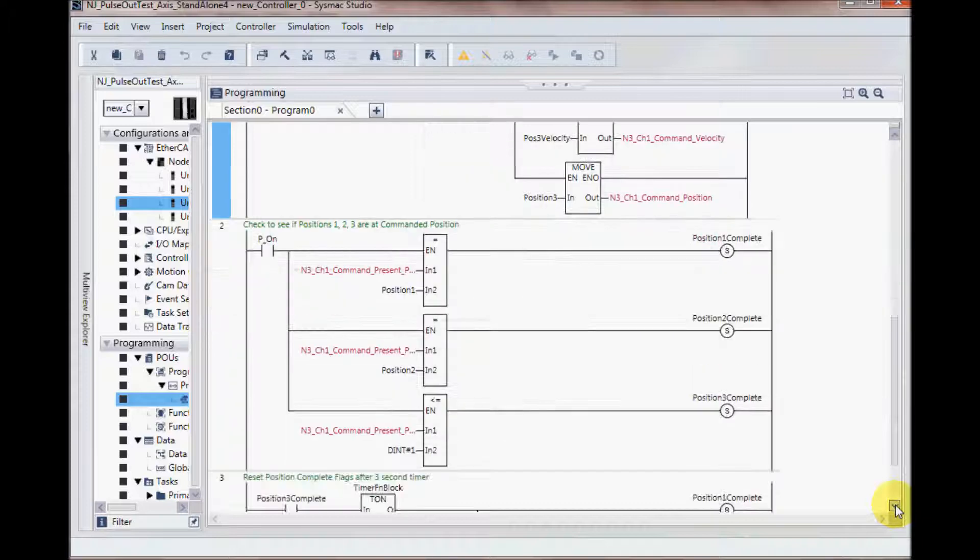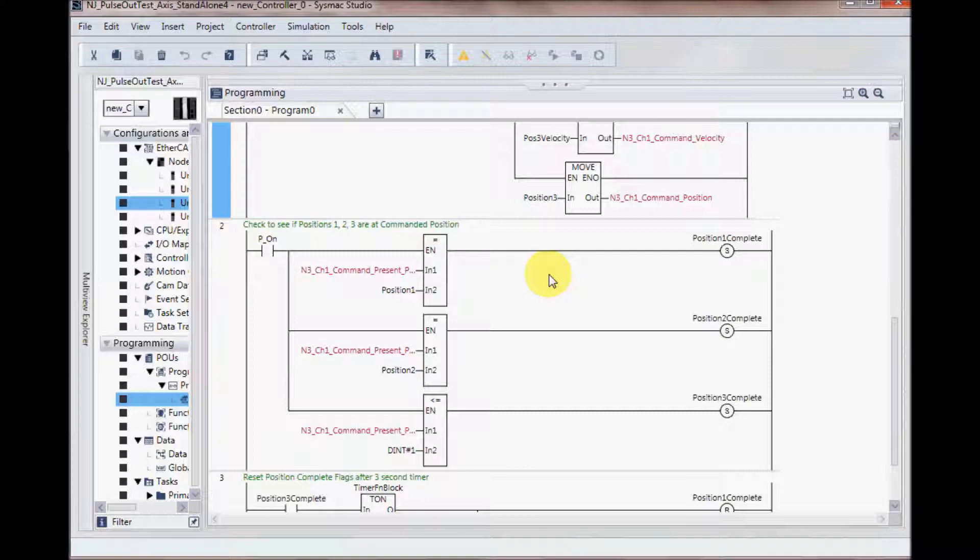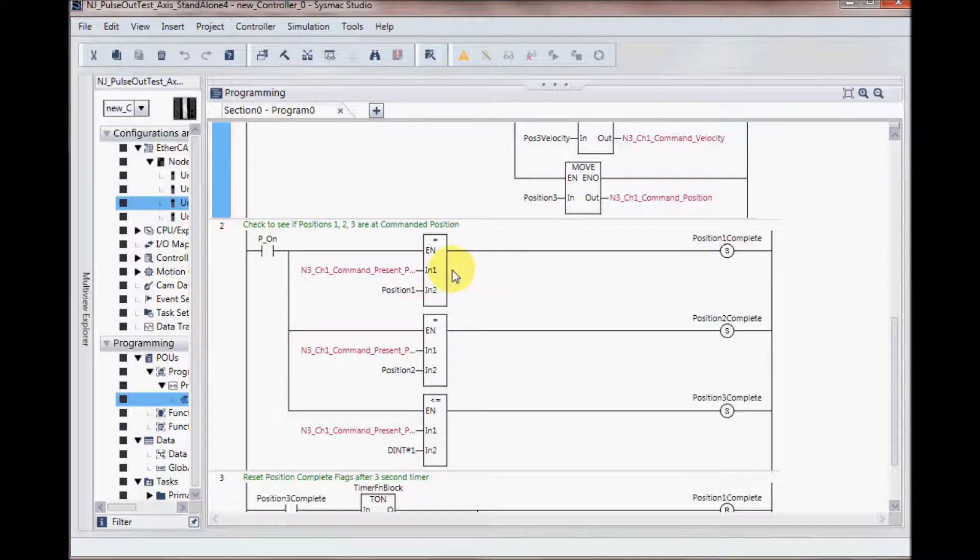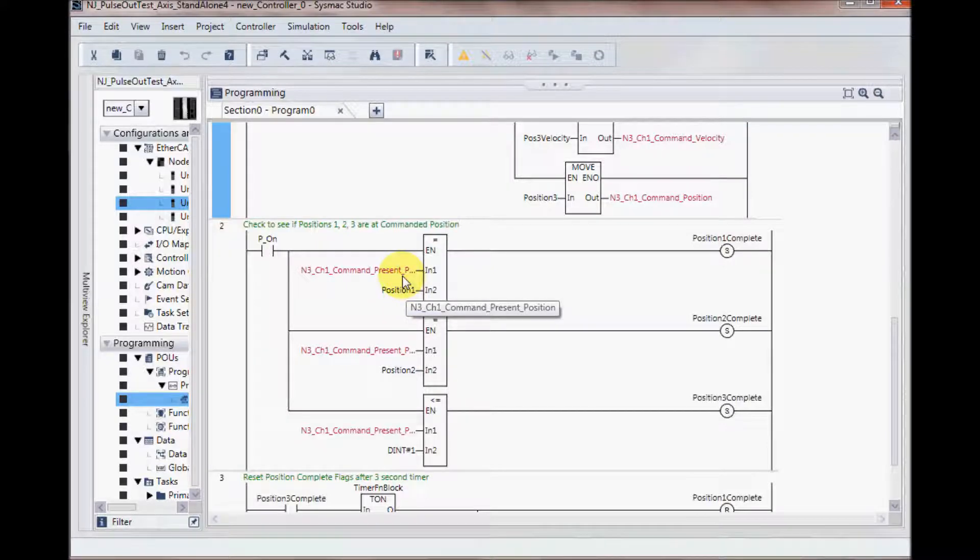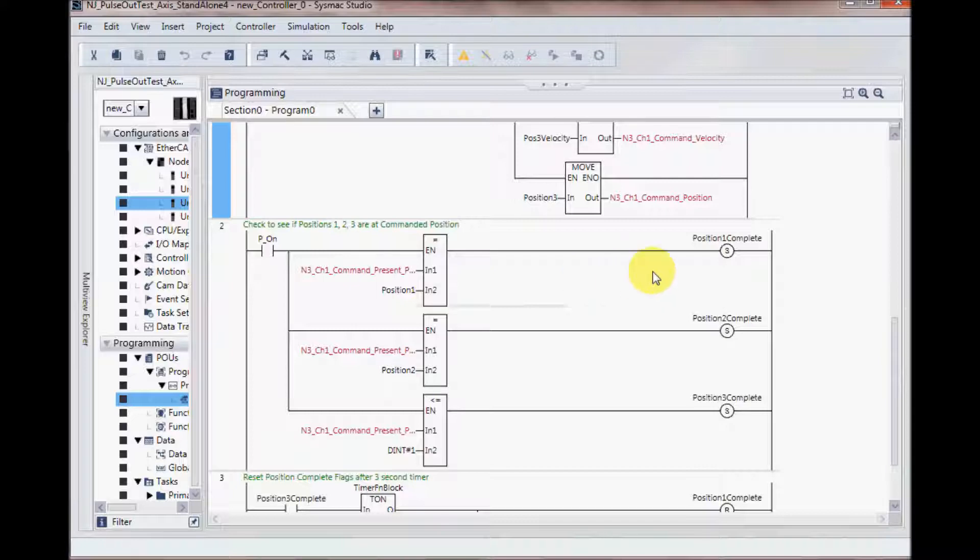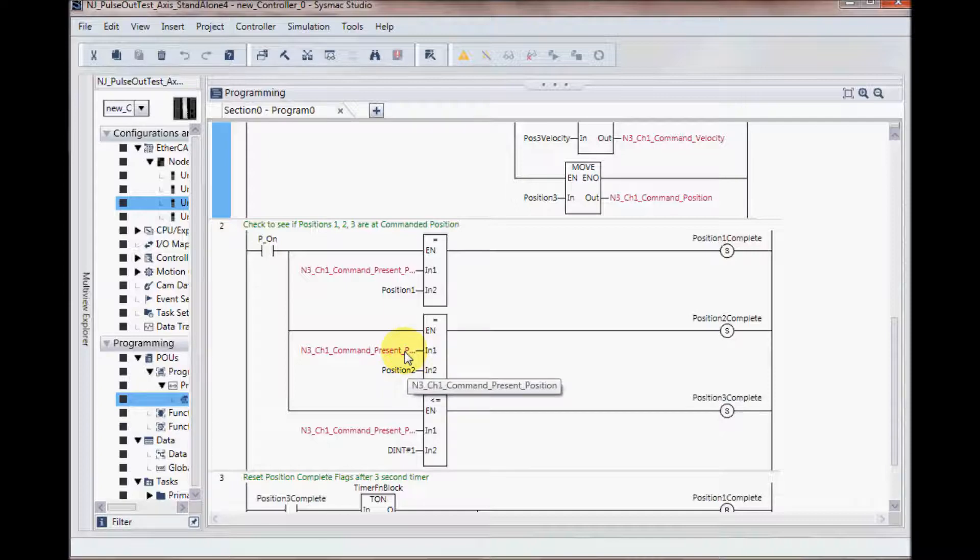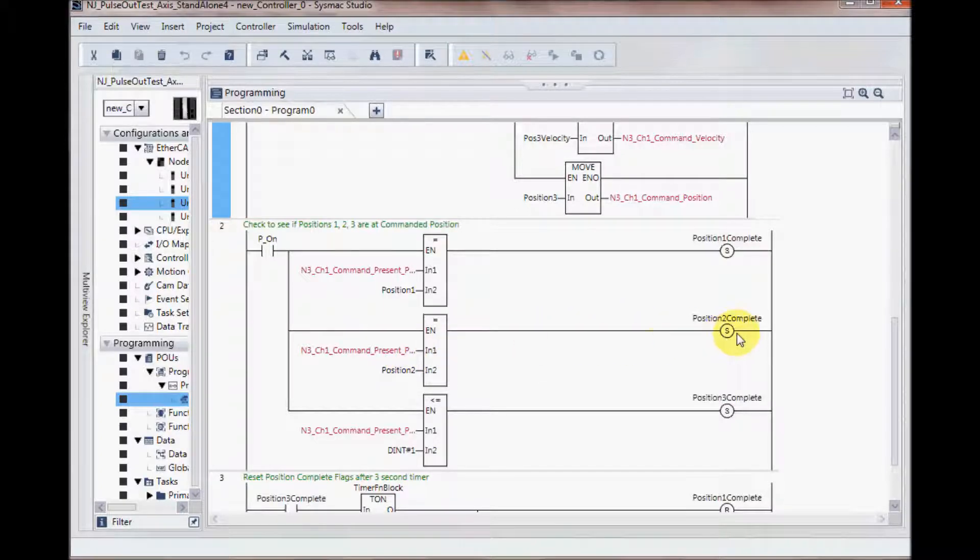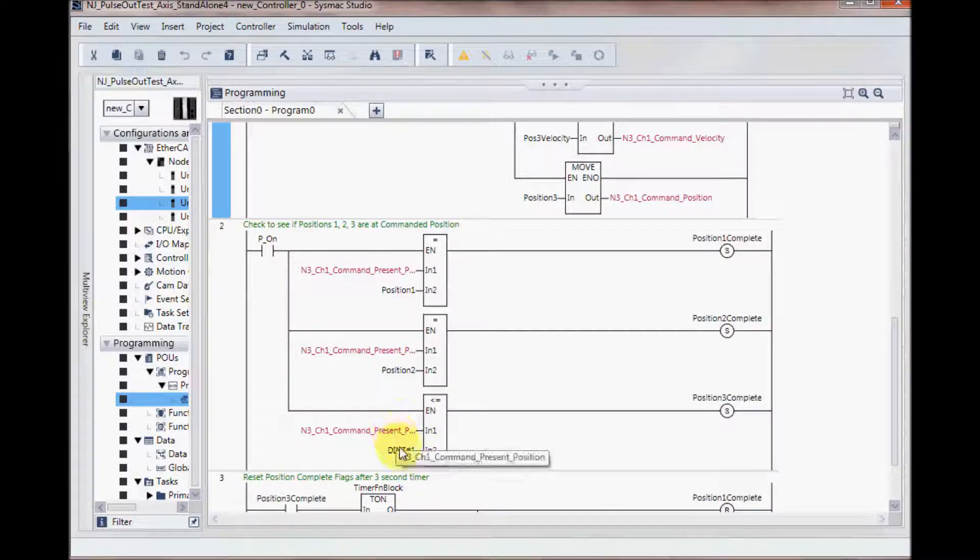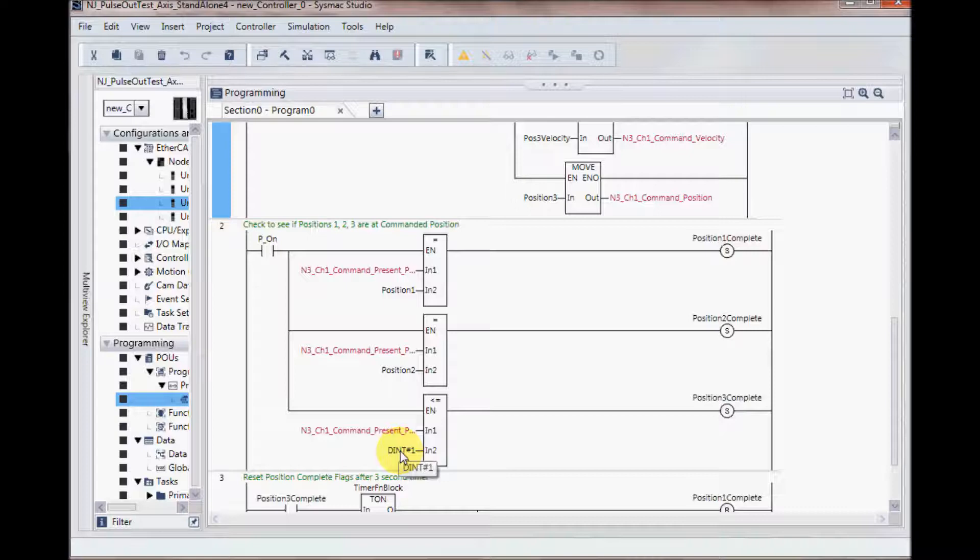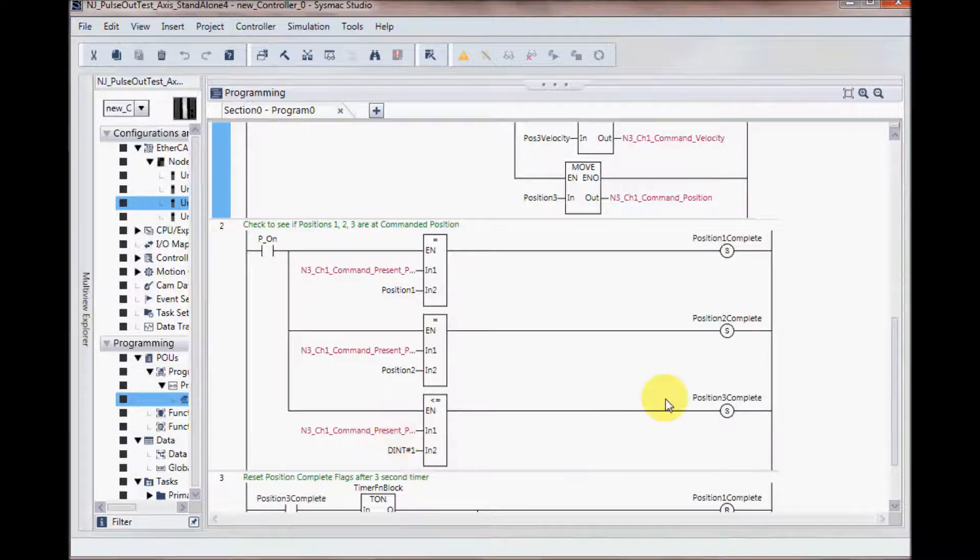And then I monitor to see if I've reached those positions. So I've got three compare statements here, looking to make sure that position 1 is equal to my commanded position. And when it is, I'll turn on position 1 complete. Same thing for position 2. When it equals the commanded position, position 2 will be complete. And then I'm looking for position 3, the same thing. When I am less than or equal to 1, so if I'm at 0 or 1, my position 3 will be complete.